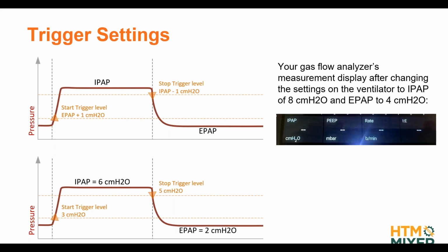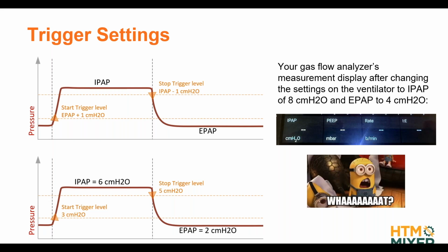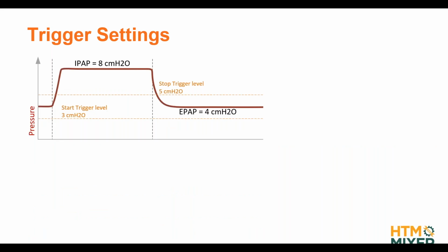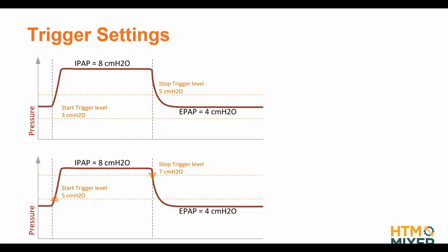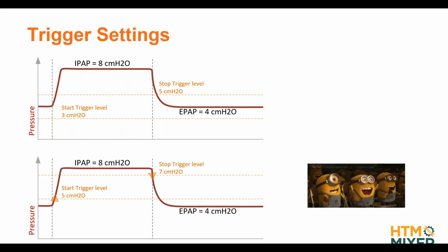As soon as I apply these settings on my ventilator, my gas flow analyzer is going to go, oop, no longer measuring any breath-based parameters, because it's no longer able to trigger. Why becomes obvious when we have a look at the updated graphics. Our start trigger level that was based on our previous settings is now so low that it's never going to be reached anymore, so it can't trigger anymore. So what we would have to do here is amend our trigger setting levels to the new situation of our ventilator settings, and then it would work again.